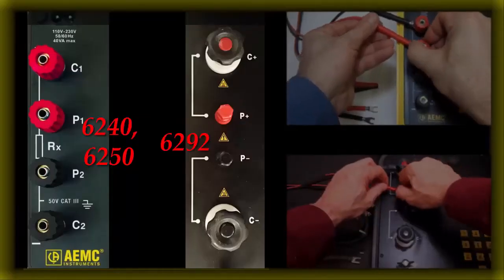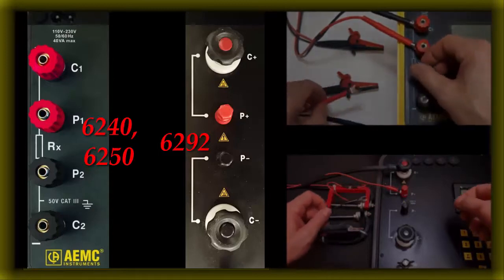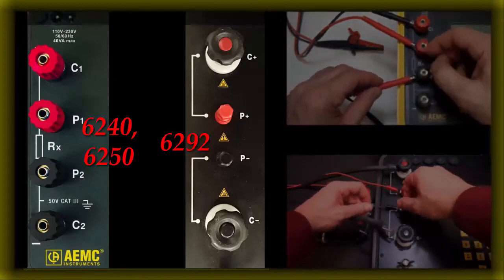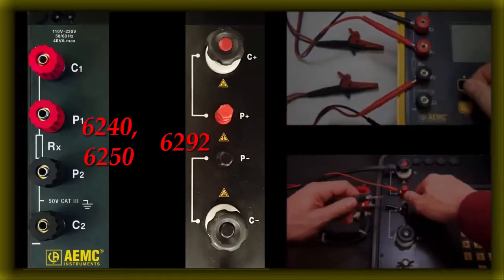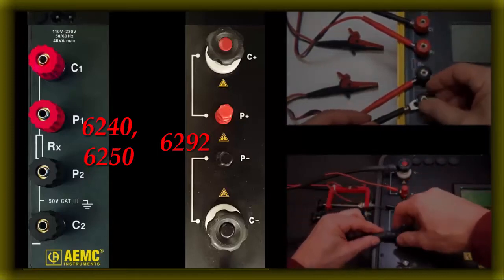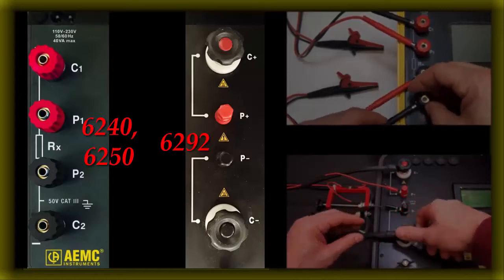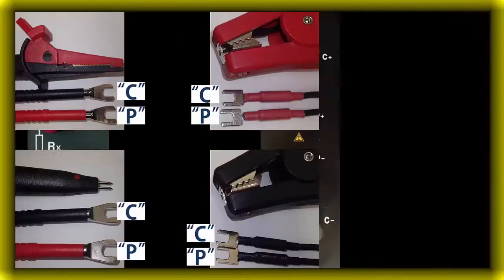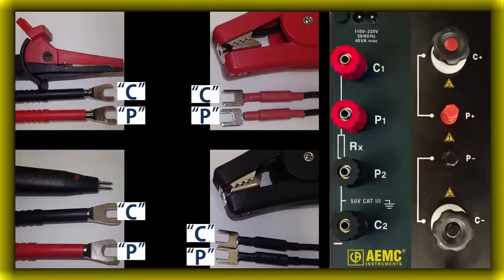Instrument front panels. All of our micro-ohmmeters have 4 terminal connections for Kelvin measurement. These consist of 2 pairs of terminals, with each pair containing a C and a P connection for current sourcing and potential sensing, respectively. 1 pair of these is red and 1 pair is black. Conversely, each handheld Kelvin probe has a current injection lead and a potential sensing lead. When connecting to the instrument, each of the handheld probe's 2 leads should be connected to a C and P terminal pair on the instrument. The same orientation should be used for each probe.